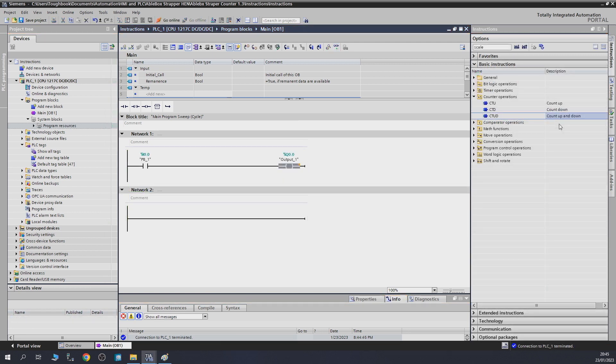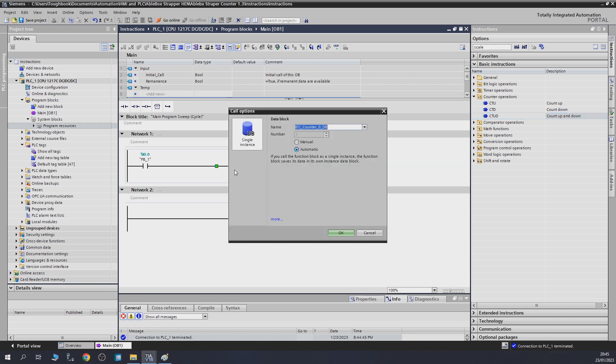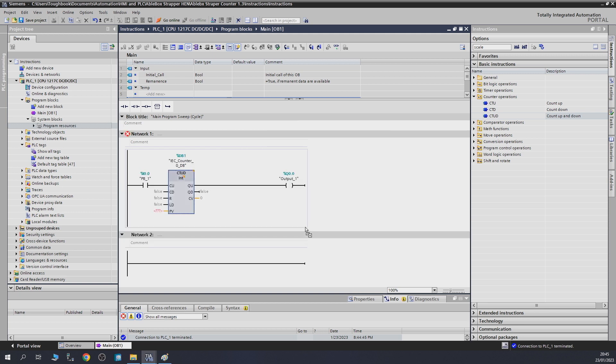To finish up the counter instructions, let's have a look at how the count up and down instruction works. Let's put that into our network with its data block. As you can see, the CU stands for count up, CD stands for count down, R stands for reset. Like our countdown counter, it needs to load its count as well to count down. From there, we're going to give it a couple of signals to test it out.